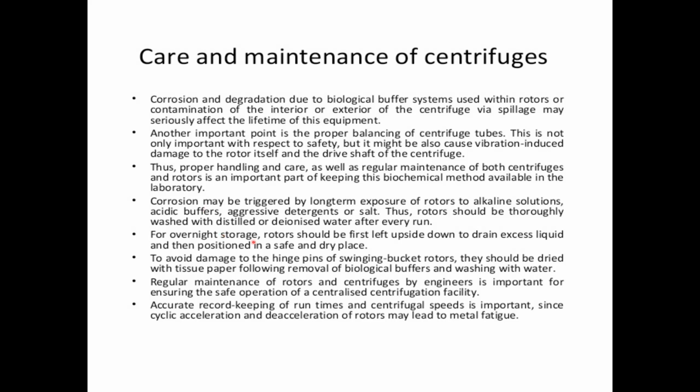The rotors, as I said, should be kept at 4 degrees. First, they should be dried, and you should take out all liquid that has accumulated, like condensed water, and put them on a dry place. Before you use them, you should pre-cool them, and you should clean them regularly.